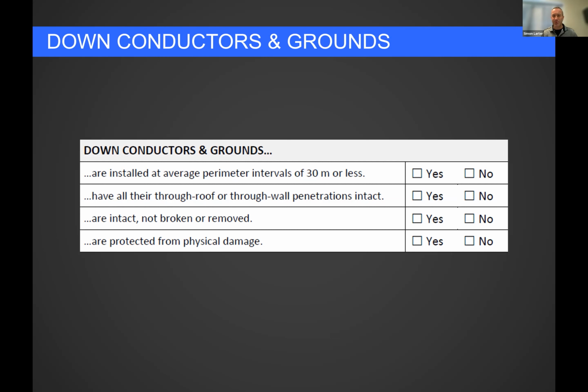lightning tends to go through the closest two down conductors. It will split and go through the closest two down conductors. Some might run through the other down conductors farther away, but it just wants to get to ground as fast as possible. That's why we don't want to spread our grounds out too much. We want to give them 30-meter intervals at most, and then the lightning will divide if it strikes and go down the two closest down conductors, the majority of the current.